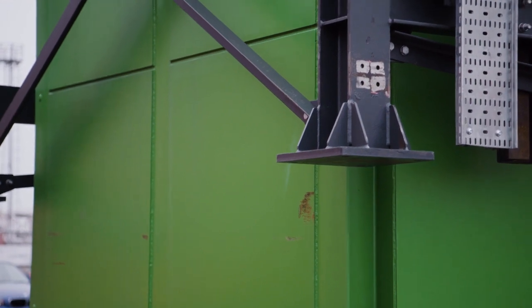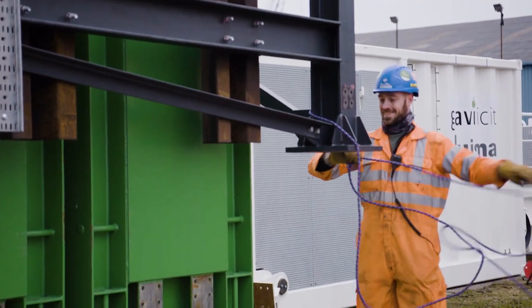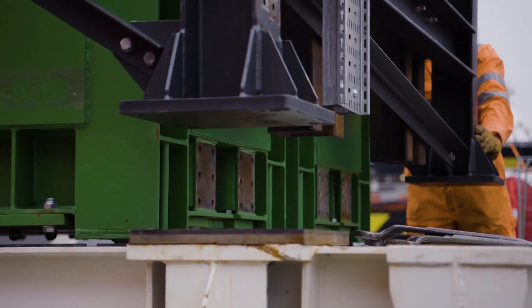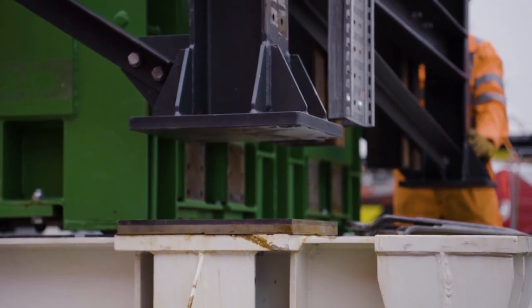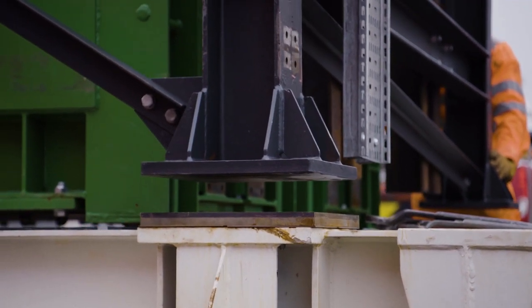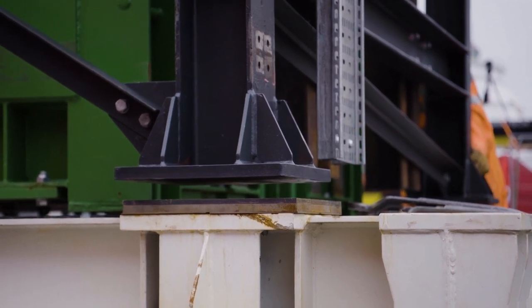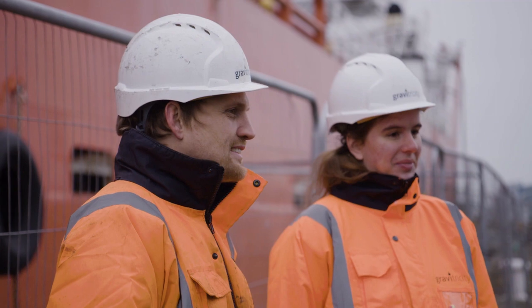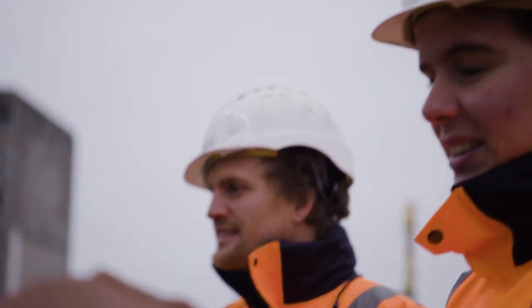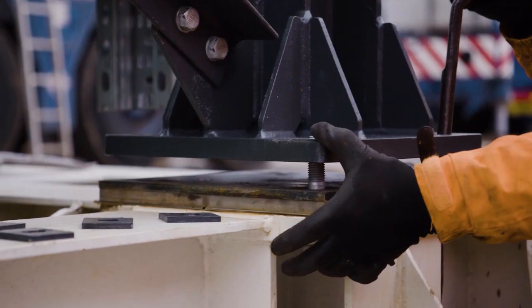What further characteristics make your technology stand out? The storage duration is a choice. We can have a very high power system that operates for 15 minutes, or a lower max power system that operates for 2, 3, 4 hours. We believe we can build a system that does 8, 12 hours plus, but we don't see a hard commercial market for that at the moment. And in other specs, efficiency, 80% round trip. So more or less as good or better than any alternatives, significantly better than pumped hydro, about the same as lithium batteries. Speed of response, sub-second.